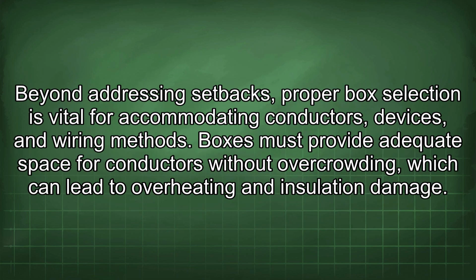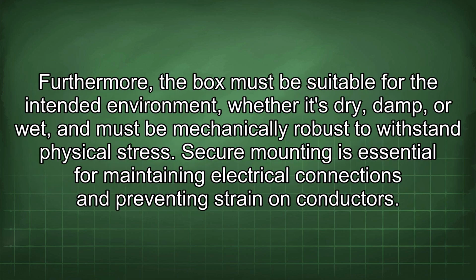Beyond addressing setbacks, proper box selection is vital for accommodating conductors, devices, and wiring methods. Boxes must provide adequate space for conductors without overcrowding, which can lead to overheating and insulation damage. Furthermore, the box must be suitable for the intended environment, whether it's dry, damp, or wet, and must be mechanically robust to withstand physical stress.